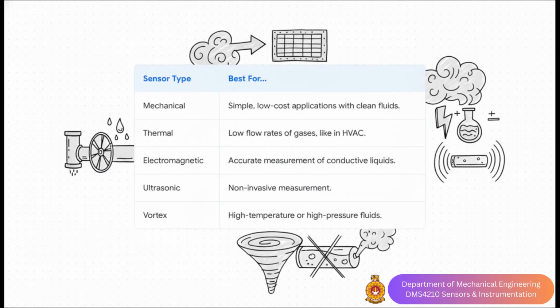So the crucial takeaway is that there's no single best flow sensor. It is all about picking the right tool for the job. If you have a simple, low-cost water line with clean fluid, a mechanical meter is probably perfect. For measuring low flow rates of air in an HVAC system, you'd want a thermal sensor. For highly accurate measurement of water, an electromagnetic sensor is the way to go. If you need to measure non-invasively from outside the pipe, ultrasonic is your answer. And for those high-pressure, high-temperature fluids like steam, the vortex meter is your champion.